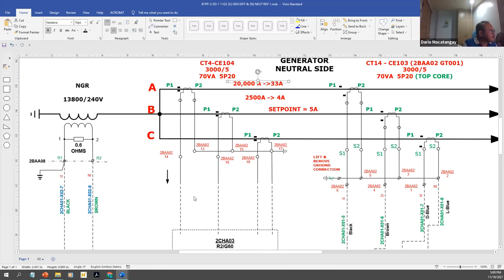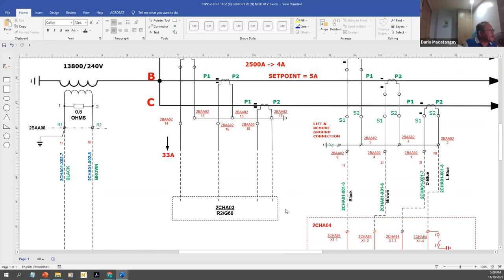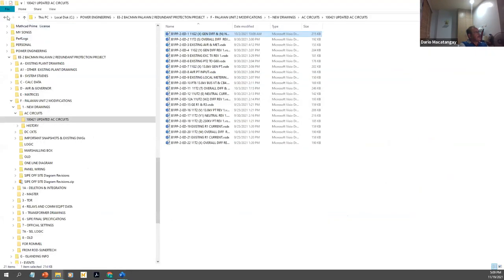So I'm going to show here. This is your 33 amps here, right? So this 33 amps goes to the relay. This is your relay here, okay? Now, when the relay sees this, it needs to trip a breaker. The relay needs to trip a breaker. So we go to another drawing now, okay? So go to another drawing here.